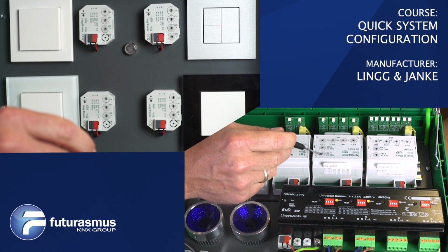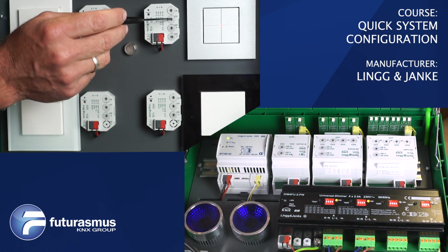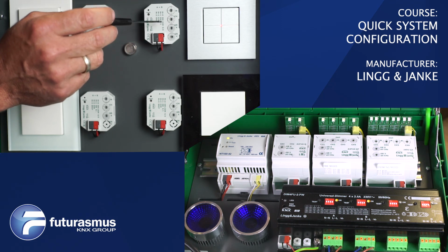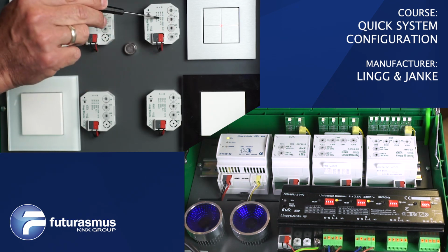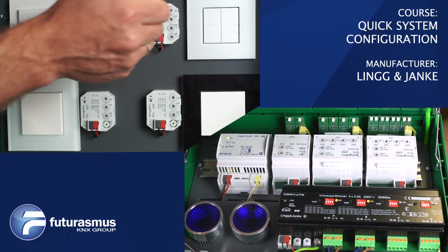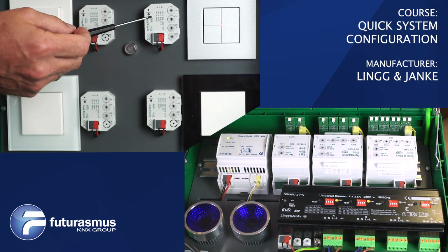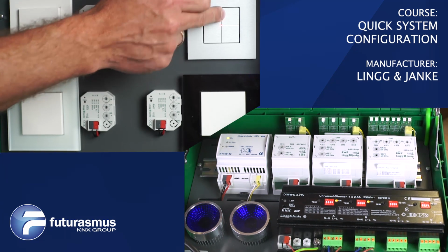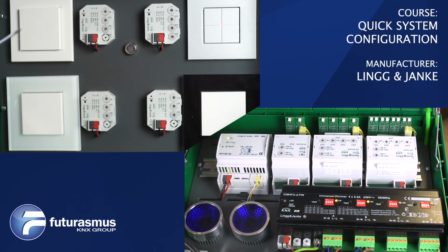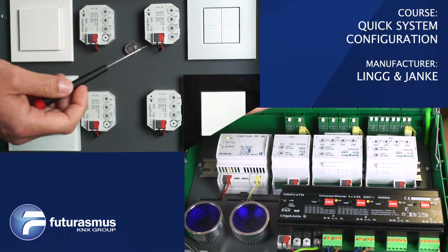The channel 4 here, I set this to 0. Okay, sorry. This one is set to 0, but I have to set it to the switching function. Okay? Now, you set the program again. As you see, if you have made a small mistake, it's very, very fast to program it again. Now, it switches on all, it switches off all. So as you see, it's very, very fast to do diagnostic also.